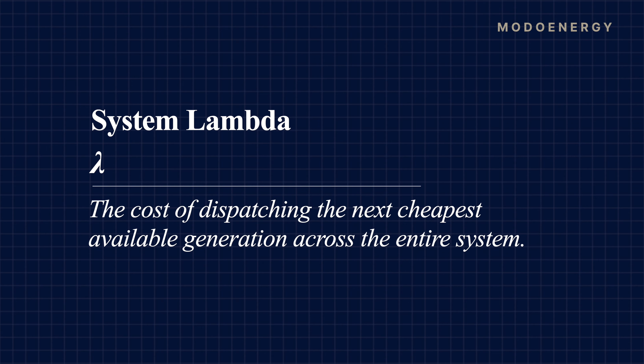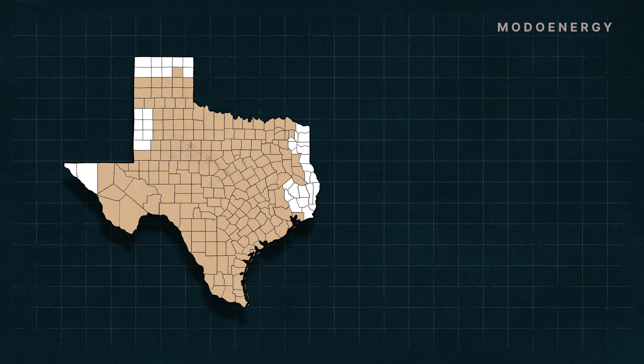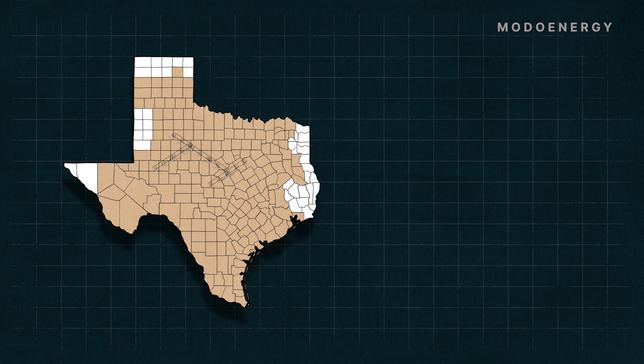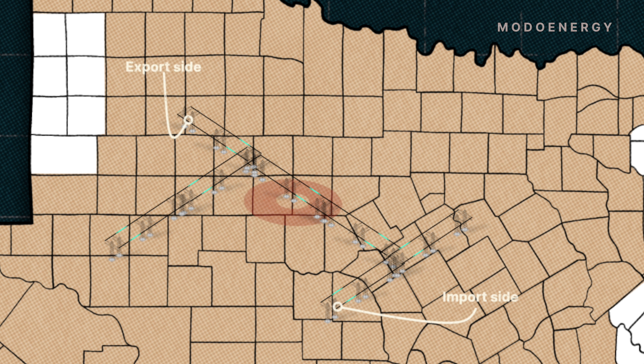However, when there is congestion, ERCOT factors it into every LMP across the system. And here's how. To begin, every congestion constraint has an import side and an export side. The constraint occurs because too much power is flowing from the export side to the import side.